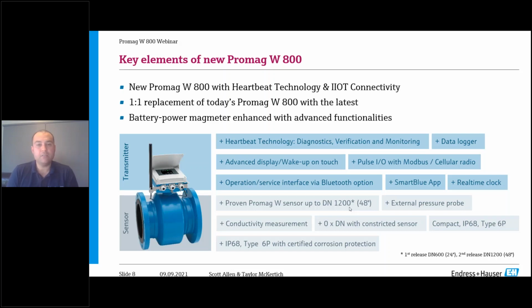Further to that, we've got conductivity measurement as well, if you're inclined to need to measure conductivity of the fluid. I mentioned earlier, 0DN is an availability that's with the Promag W800 as well. In applications with tight spaces where your traditional 5 times pipe diameter upstream isn't possible, 0DN is available. The last piece is fully IP rated for applications where you're burying underground or in pits where they can be flooded. IP68 is fully available as well.